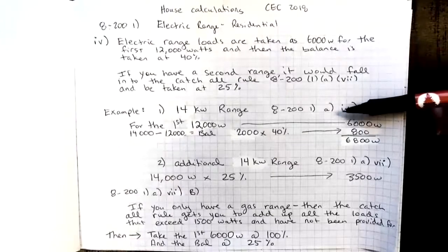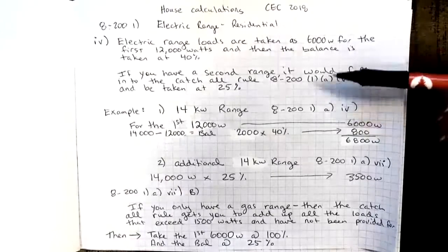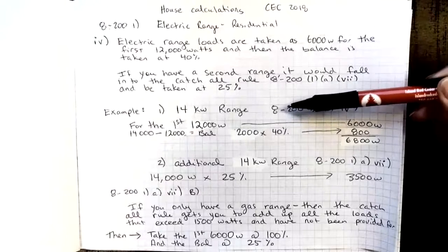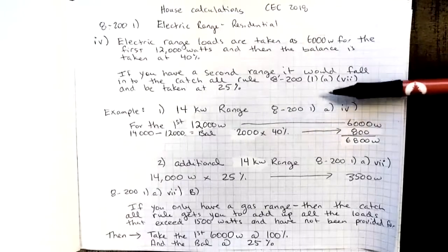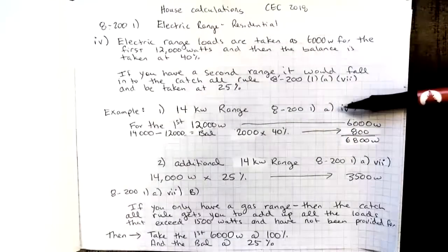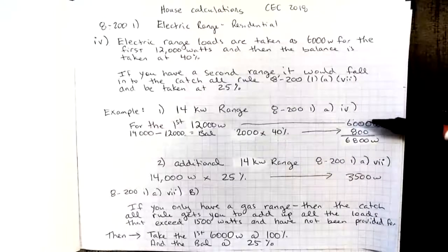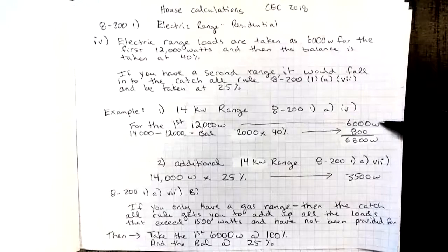So for example, I have two ranges in this home. They're both 14,000 watt ranges. The first range would fall under 8201A4, which means for the first 12,000 watts of that 14, we would apply a demand factor of 6,000 watts.